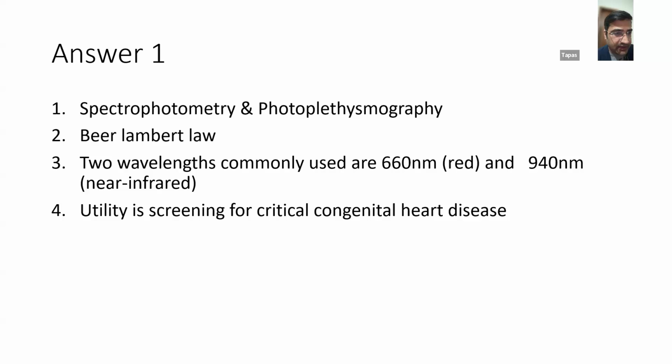So when you apply the pulse oximeter probe, the red and infrared light are projected through the skin, and are absorbed by the deoxyhemoglobin and oxyhemoglobin based upon their concentration. The amount of light that reaches the photodetector after being absorbed is measured. Based upon the amount of light transmitted, it detects the ratio of deoxyhemoglobin to oxyhemoglobin. So this is known as spectrophotometry.